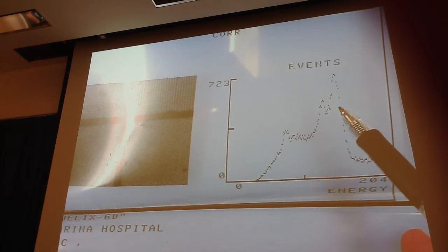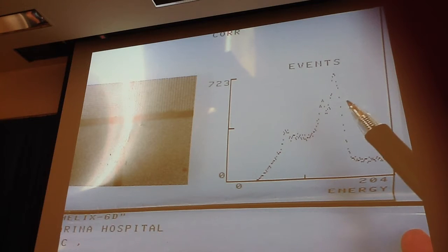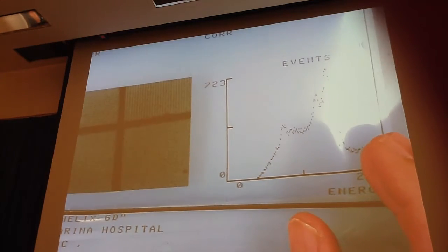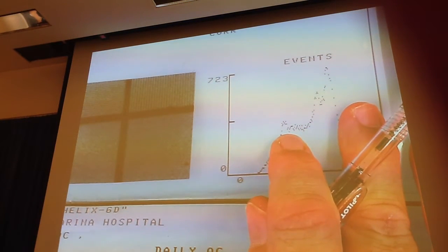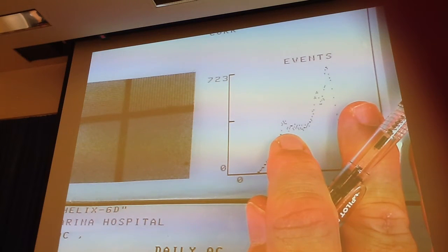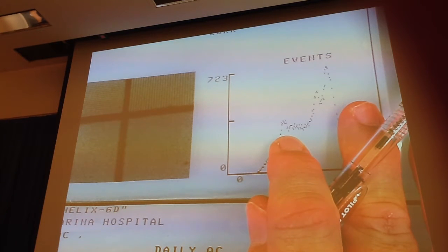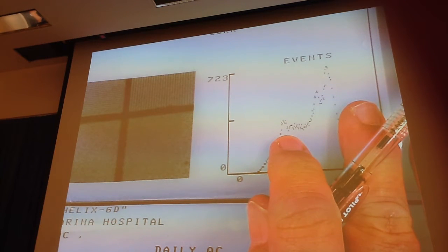Okay? I have a question. Yeah. What if you had a point source that was in the background, when you didn't have it shielded at all, would the gamma camera pick it up, especially if it was intrinsic like that? Yeah. In fact, what some technologists do before they put the collimator on, if they're going to do an extrinsic flood, while the collimator is off, they'll do an acquisition just to see if there's any contamination in the room being picked up by the gamma camera.